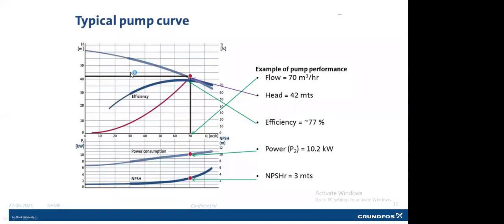And we always need to make sure the pump is selected at the best efficiency point. While installing a new pump, if we need to check at which duty parameter the pump is operating, we can simply check the pump head by installing a differential pressure gauge across the pump, and we can check the respective flow at which the pump is operating. Let's say for example the pump is designed for 42 meters, and if it is operating at 50 meters of head, here we can correlate that the pump is operating at 50 meter cube per hour flow at lower efficiency than the design, and it is consuming 8 or 8.5 kilowatts of power.